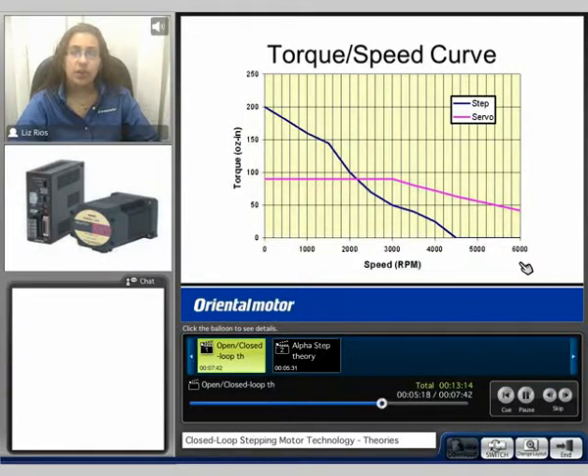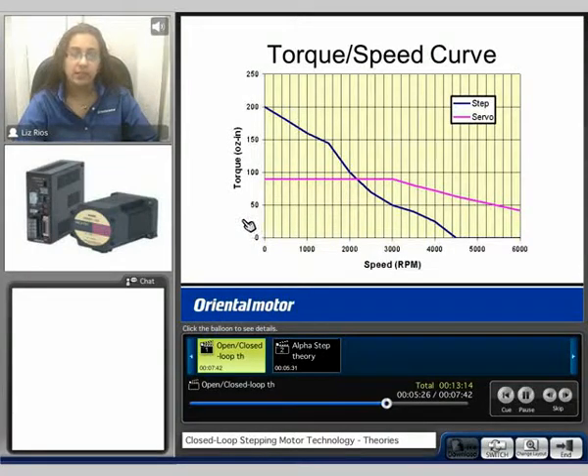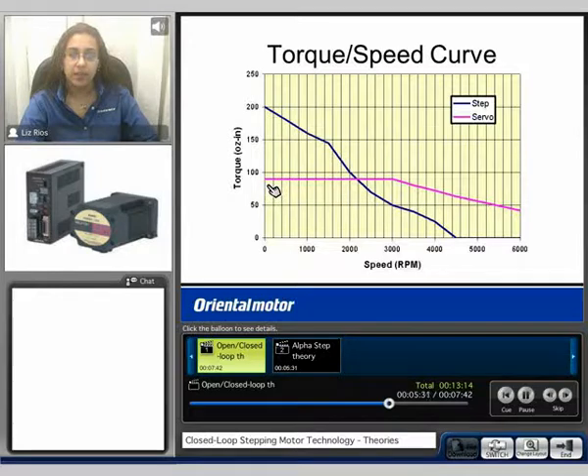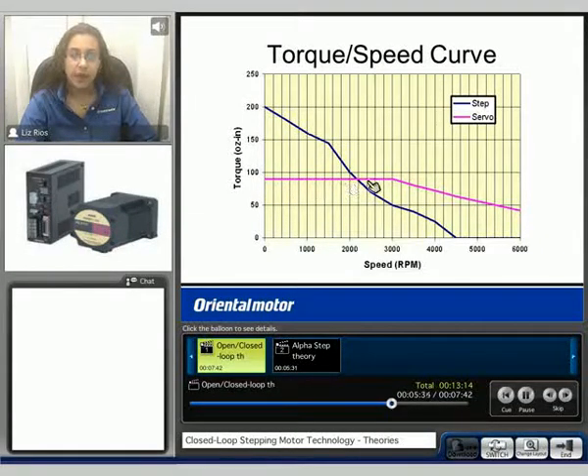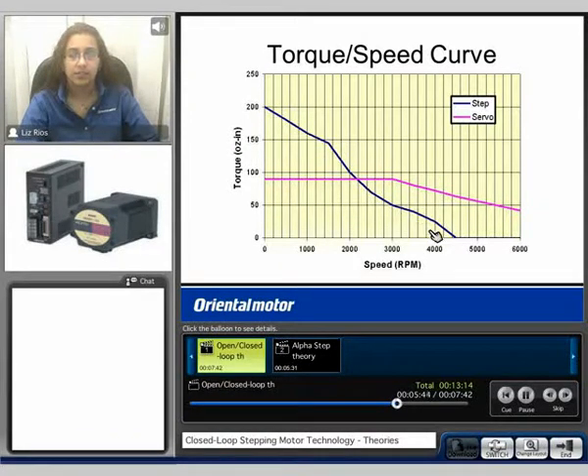Here we compare a torque and speed curve. We see the speed represented on the x-axis in RPM, and the torque represented on the y-axis in ounce inches. We can see the servo system, represented here by the pink line, has low starting torque but is able to run out at higher speeds. Whereas the stepping motor, represented here by the blue line, has high starting torque, but as we increase speed our torque decreases. These are characteristics of each.